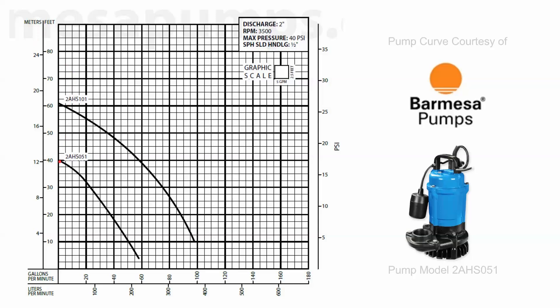At half horsepower this pump will produce a shutoff pressure of 40 feet, and at the one horsepower version roughly 61 feet. On the flow side, the maximum flow rate of the half horsepower is about 55–56 gallons per minute, and the one horsepower is roughly 95–96 gallons per minute. You can tell that the increase in work is a direct correlation of the flow and head performance of the particular pump.